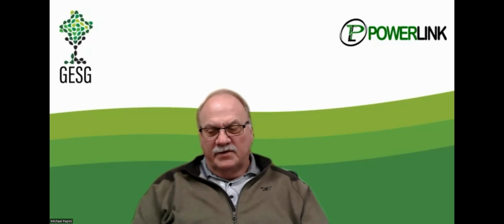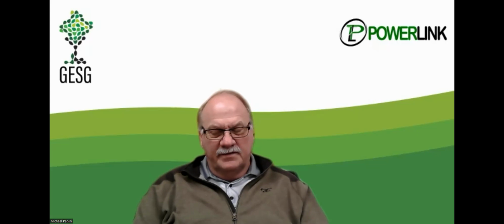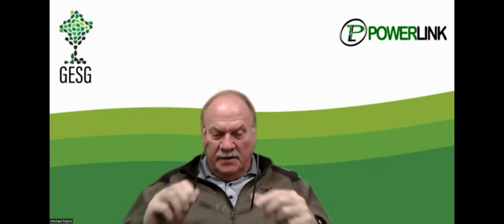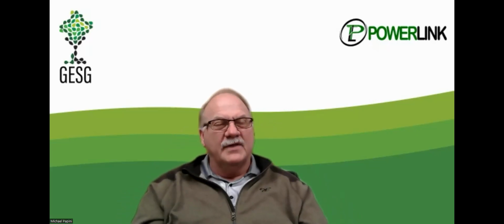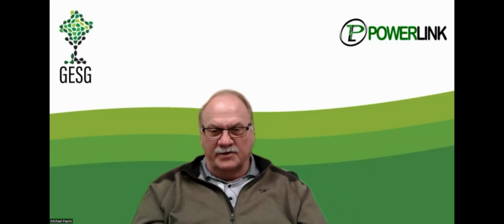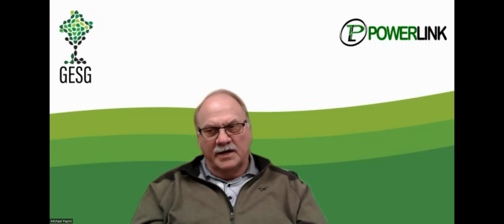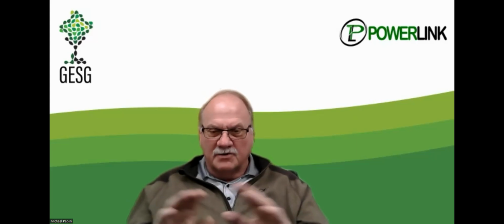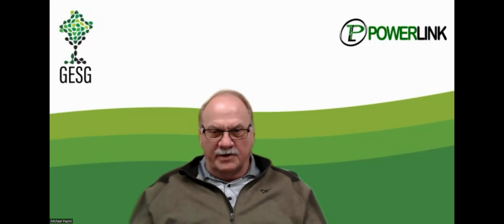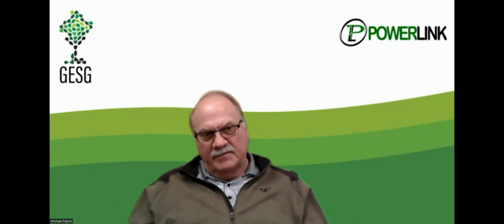Correct. Yeah, it's tough to be in this right now because of all the fraud going on, and people who don't really do this all the time but know enough about electricity to say something, and then right away the engineer from the power company goes, 'Well, here's the power triangle, this is how it works, and you're not saving anything because we're not charging for kVA.' But the problem is, when I was at that meeting yesterday, I had to tell the guy a number of times that the power triangle is fine, but you're not taking into account the watts that are created by heat. You're looking at watts per horsepower, not watts by heat. And he's like, yeah, okay, I see what you mean.